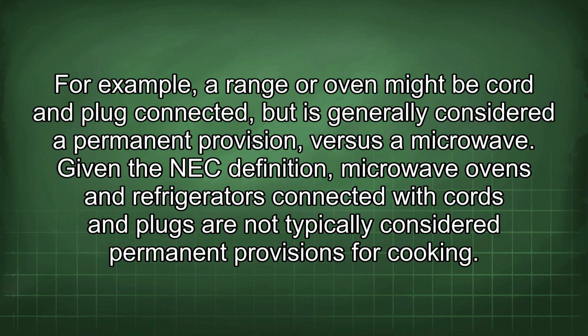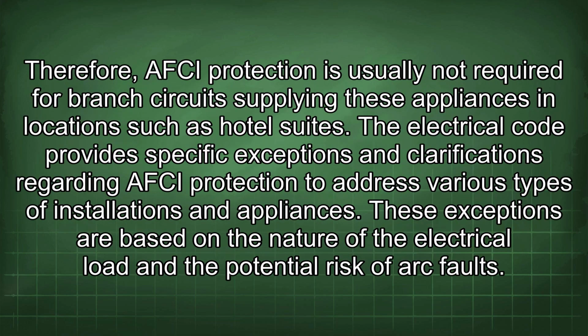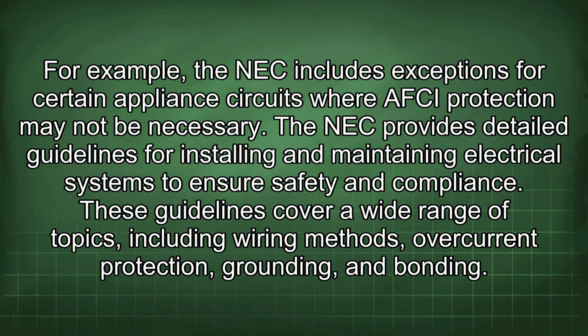For example, a range or oven might be cord and plug connected, but is generally considered a permanent provision, versus a microwave. Given the NEC definition, microwave ovens and refrigerators connected with cords and plugs are not typically considered permanent provisions for cooking. Therefore, AFCI protection is usually not required for branch circuits supplying these appliances in locations such as hotel suites. The Electrical Code provides specific exceptions and clarifications regarding AFCI protection to address various types of installations and appliances. These exceptions are based on the nature of the electrical load and the potential risk of arc faults. For example, the NEC includes exceptions for certain appliance circuits where AFCI protection may not be necessary.